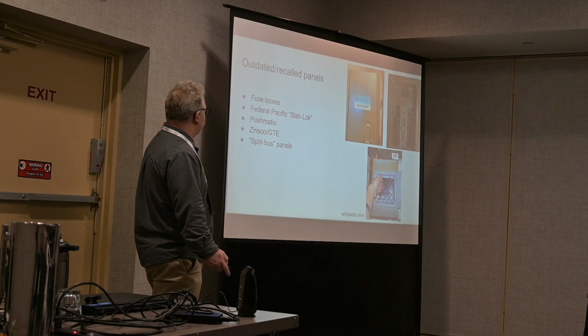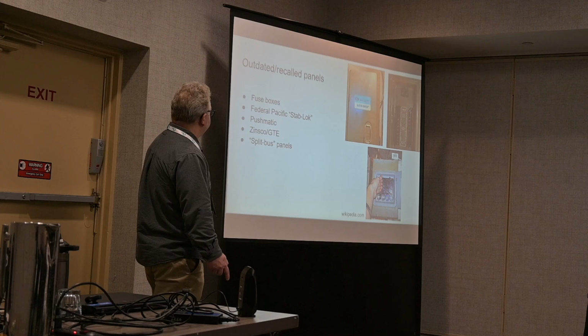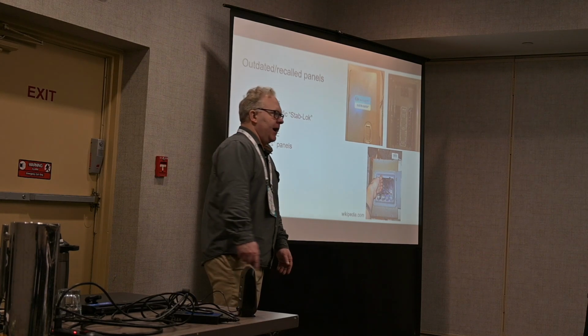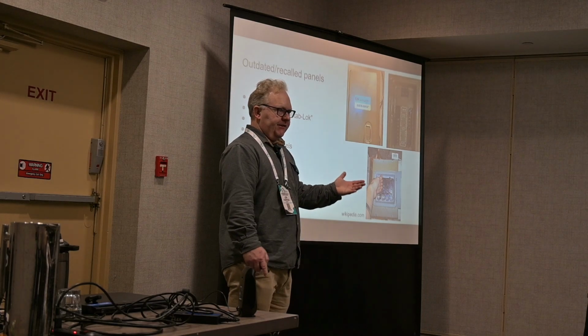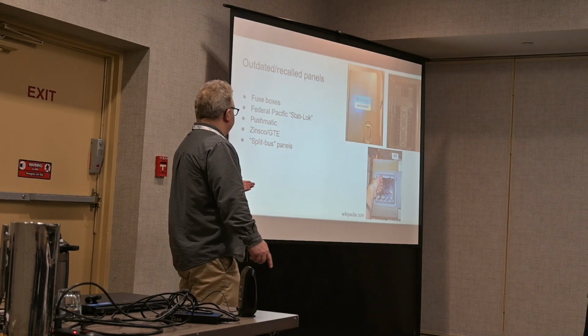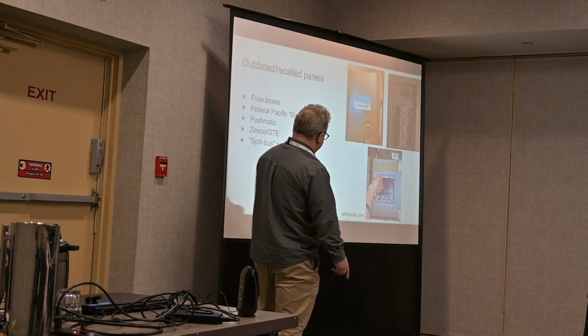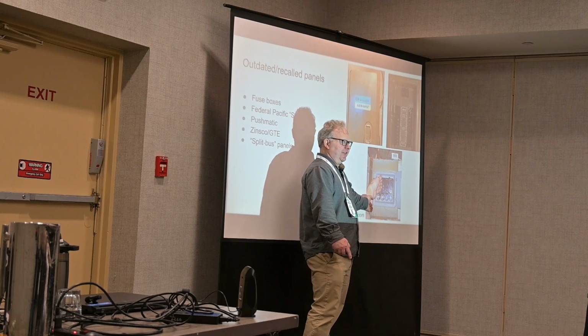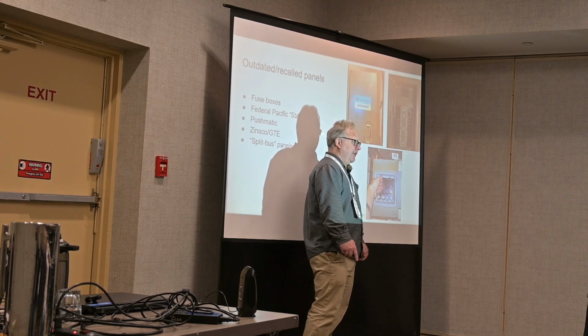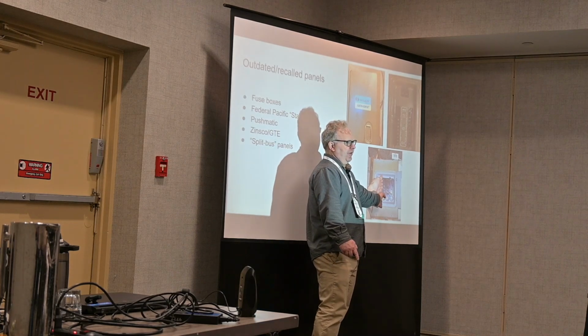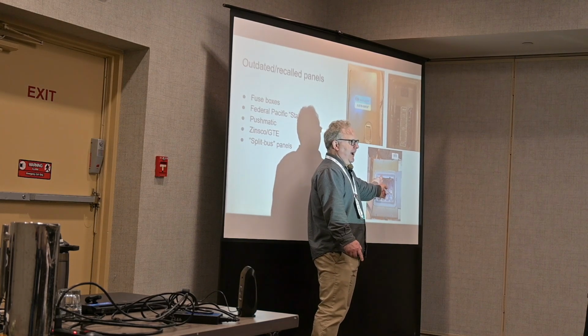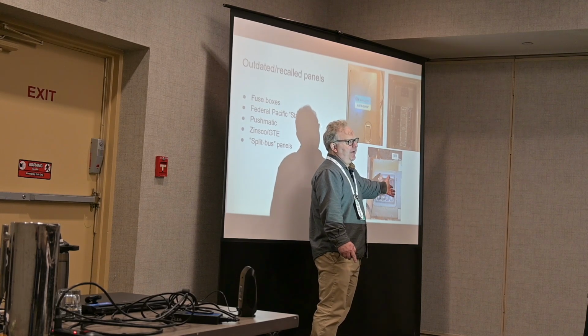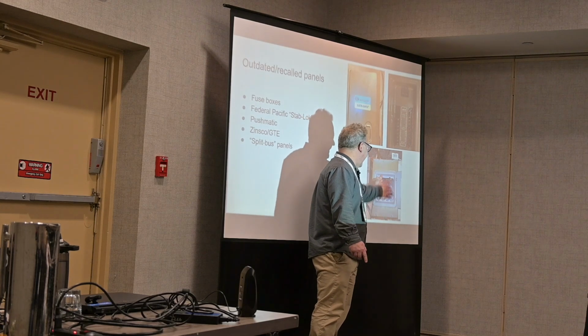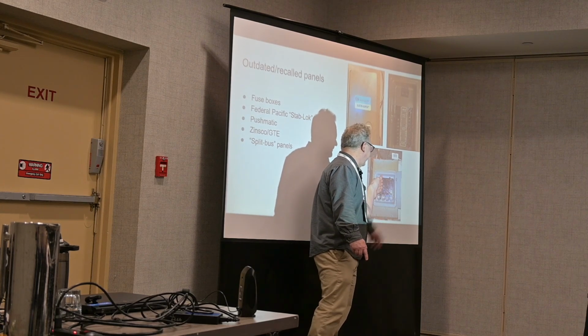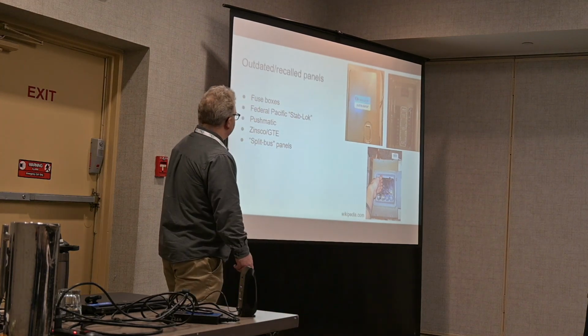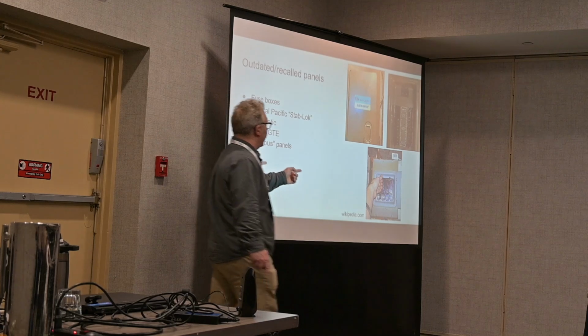We also want to have our heads up for outdated and recalled panels. A lot of these things were installed in the 60s and 70s, and have been recalled for one reason or another. Is anyone still running into these 60 amp fuse panels? Yeah, we see those. These are absolutely going to need to be upgraded. It's time, and they're typically 60 amps, so they don't have enough capacity anyway, and no way to safely add additional load. So that's pretty much an automatic upgrade. But there are other brands that have been recalled.